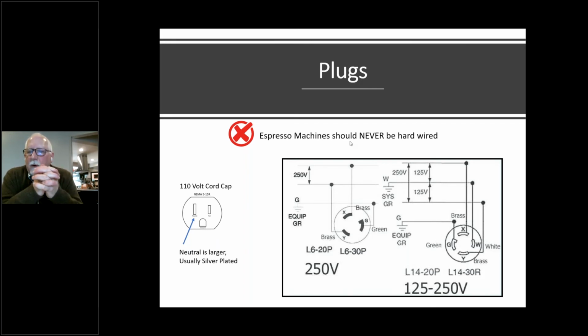You will occasionally find 4-wire plugs, especially for coffee brewers. And it's essentially the same thing as a 3-wire, like an L6-30 or an L6-20, but it actually carries a neutral as well. And that neutral wire is what allows you to provide 110 volts to various components of the machine in addition to the 220. The neutral wire is always opposite the ground, and the ground always has the dog leg. And that neutral wire, again, it really only applies to brewers.